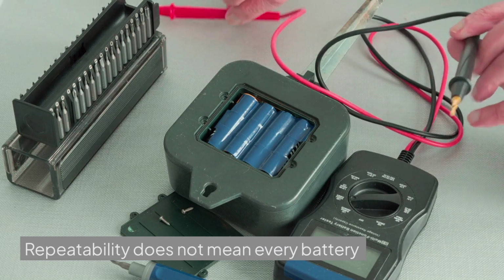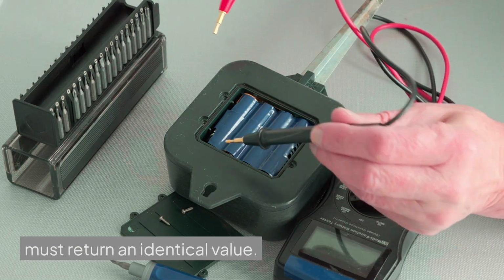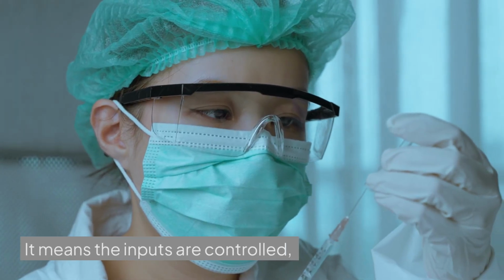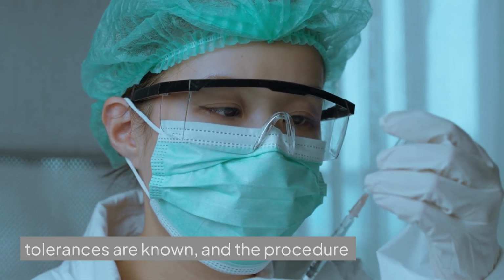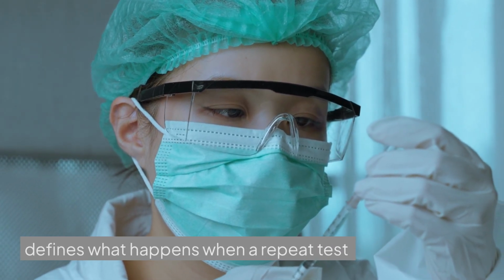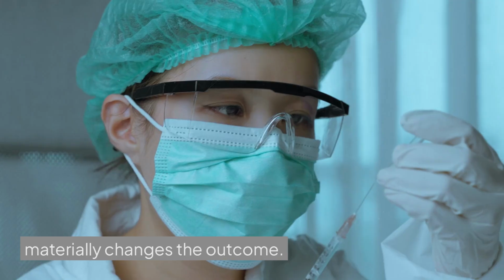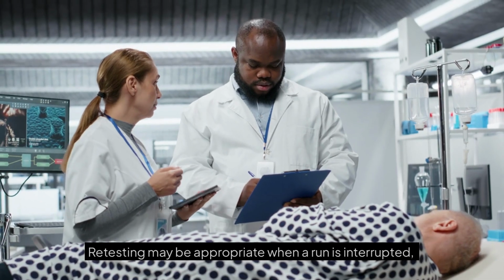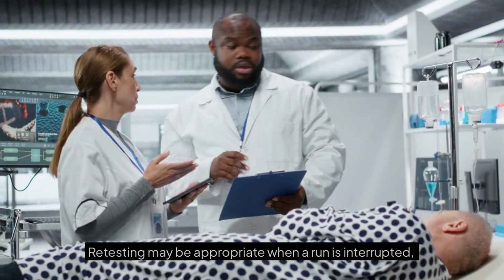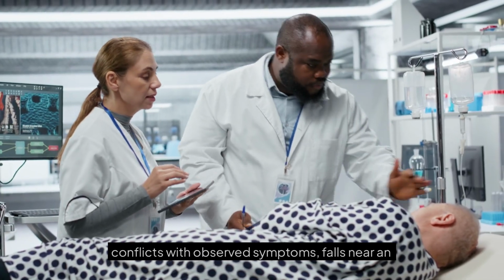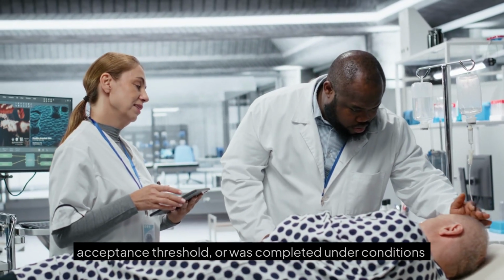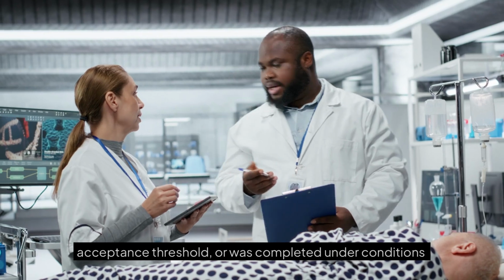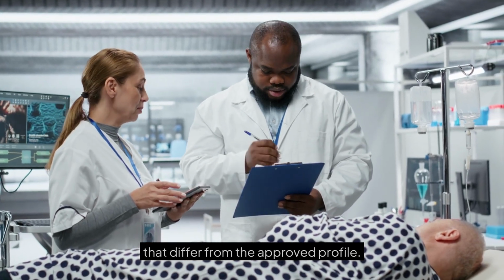Repeatability does not mean every battery must return an identical value. It means the inputs are controlled, tolerances are known, and the procedure defines what happens when a repeat test materially changes the outcome. Retesting may be appropriate when a run is interrupted, conflicts with observed symptoms, falls near an acceptance threshold, or was completed under conditions that differ from the approved profile.